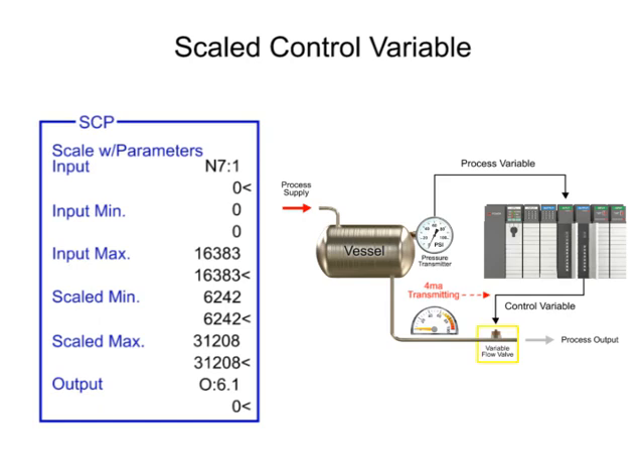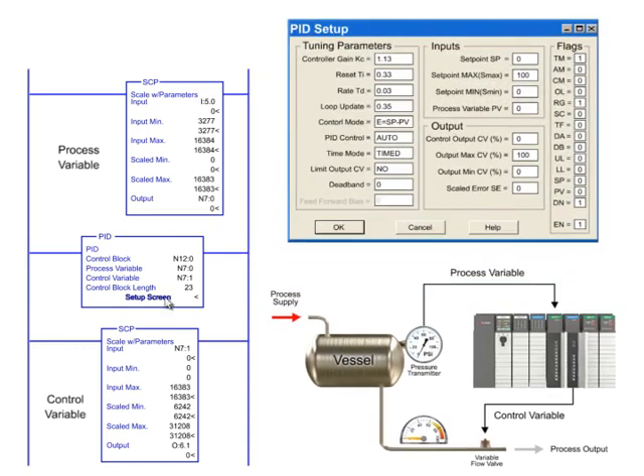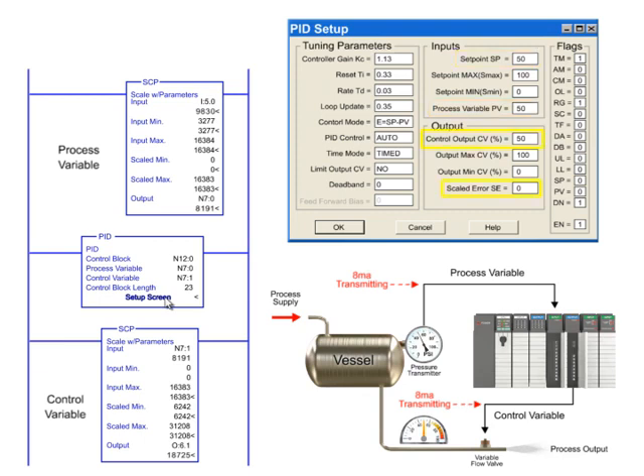The analog signal is then sent to the flow valve where the operating range is adjusted between 0 and 100%. With the data scaled using the SCP instruction, the process of controlling the pressure of the vessel to 50 PSI continues by entering the setpoint of 50 in the PID setup menu. As the PID instruction is executed, a scaled error is generated by subtracting the process variable from the setpoint. By increasing the control output, the error is reduced to attain the setpoint as the PSI is raised in the system. In other words, the valve position is gradually closed to reduce the pressure loss. Upon reaching the setpoint in the system, the control output and scaled error is reduced to zero.